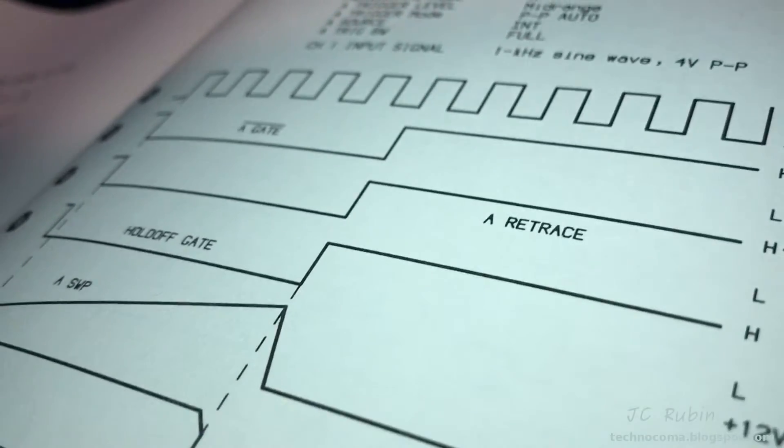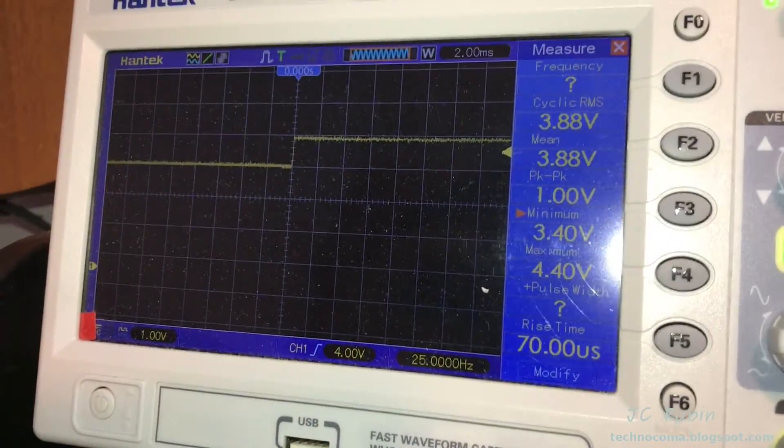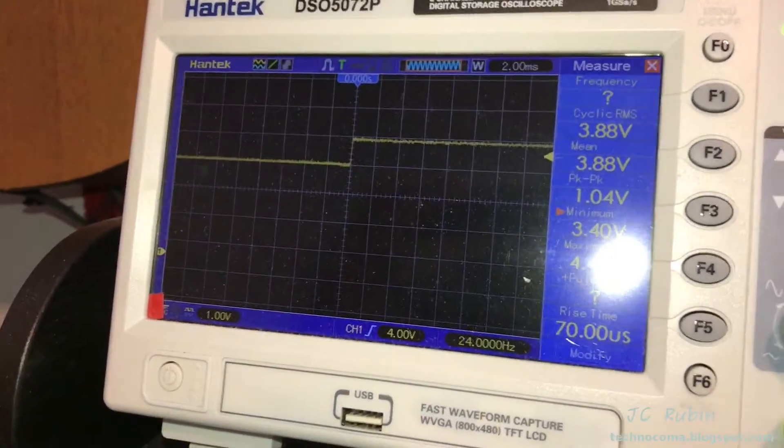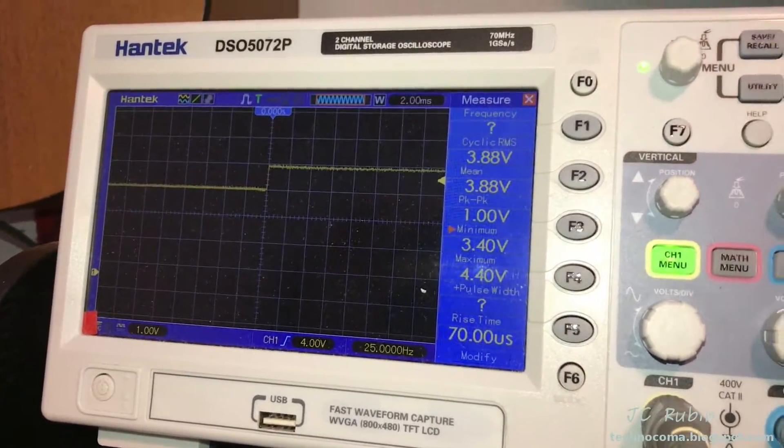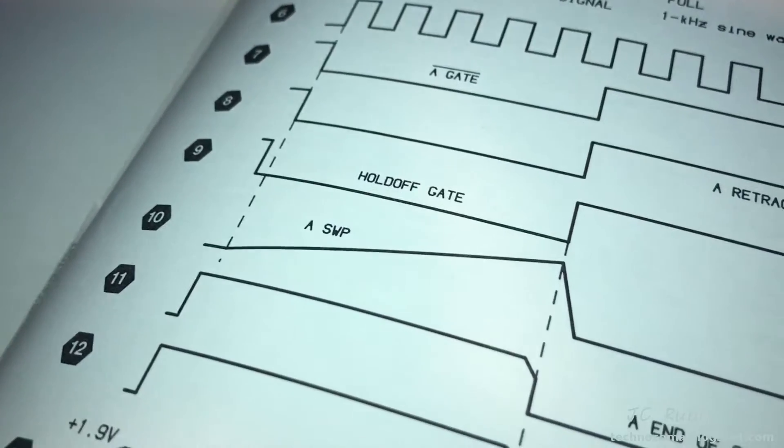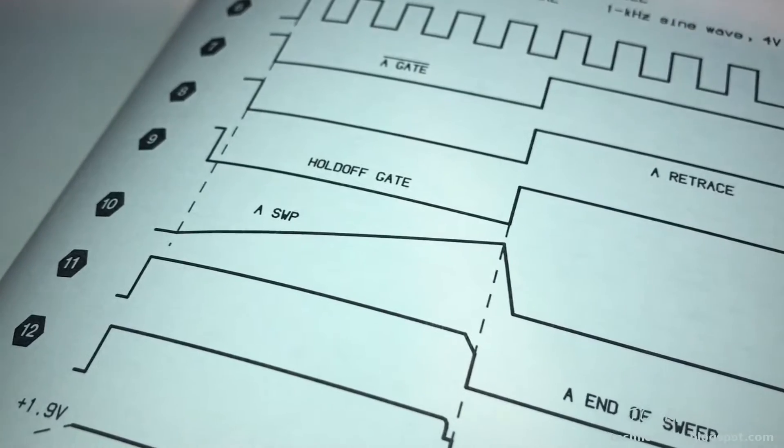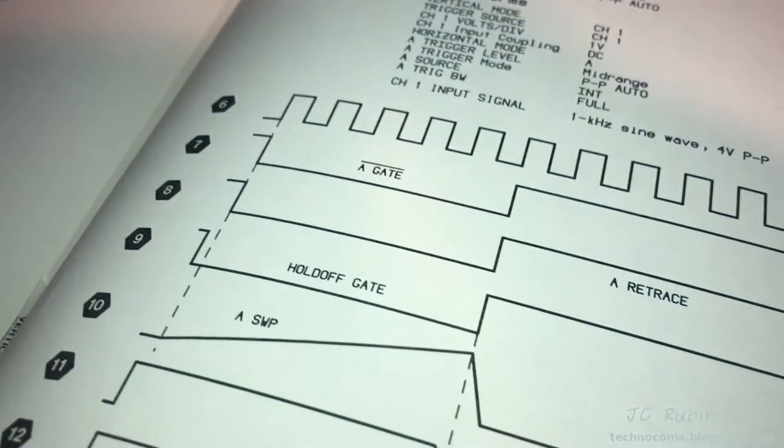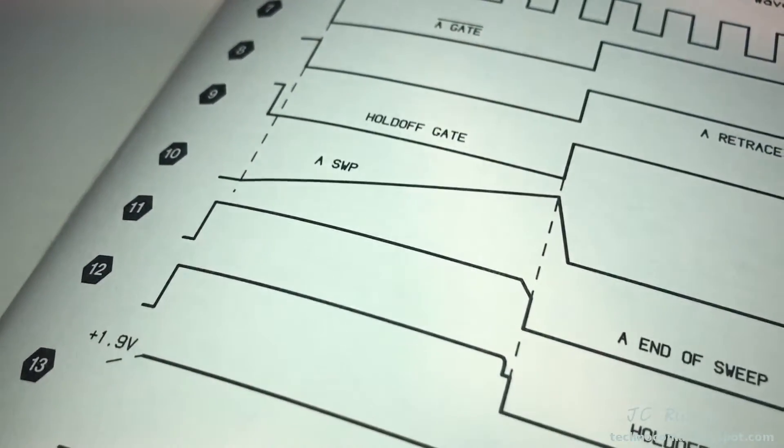Test point nine, this is a hold-off gate, and it looks exactly as it does. Very stable, I don't see any issues there. Skip 10 for now and come back to it because it's on the actual trigger board.